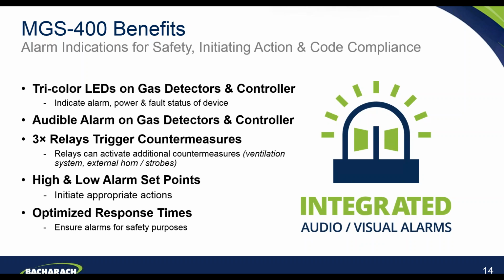On the 450 and the 460 variants, they have 3 alarm relays. So the relays can be used to activate additional countermeasures, such as activation of mechanical ventilation system, or used to connect to external horns and strobes. All of the MGS-400 series detectors offer fully configurable high and low alarm set points. So that's designed to initiate appropriate actions at those alarm set points. And again, they are fully configurable, which enables our customers to set those according to their own site conditions and site requirements.